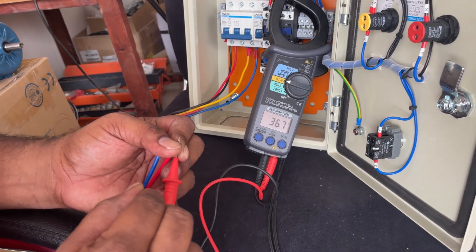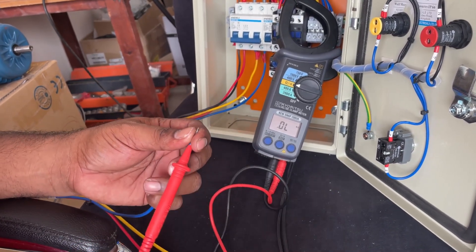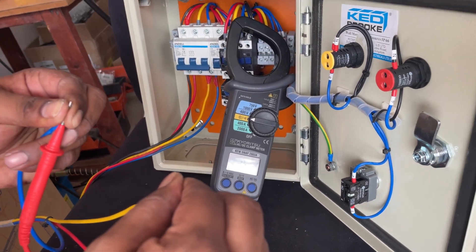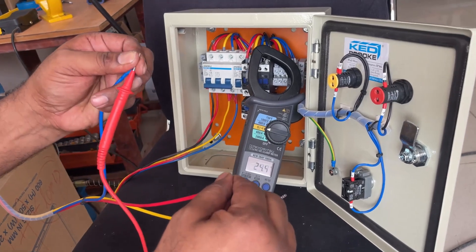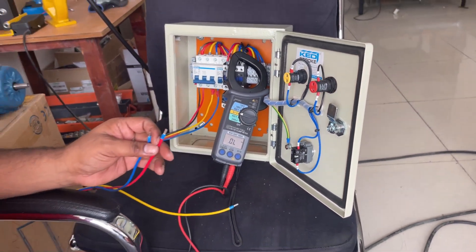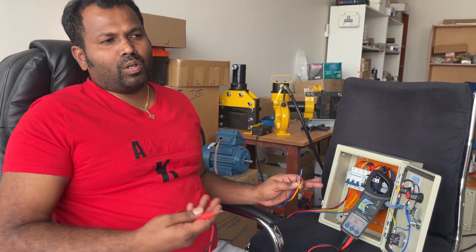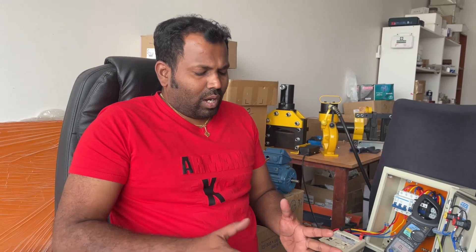It is showing 36.7 ohms — that is R to Y. Now we check Y to B, which is also showing almost the same: 36.6 ohms. A difference of 0.1 is not a problem. Now checking B with R — it is also showing the same value. That means the coils are okay. If any two coils were shorted, the value would show differently, and that would confirm the winding is shorted internally.